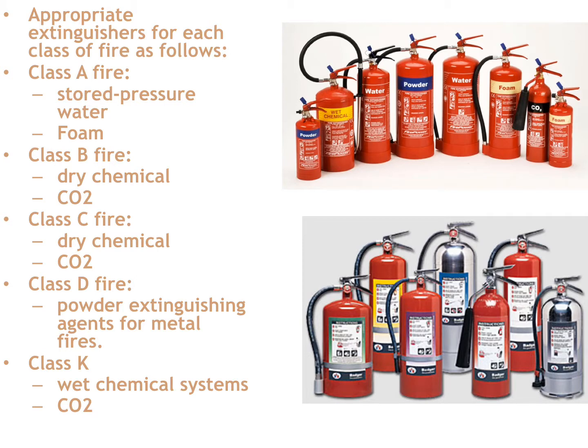The water with foam is going to help cool and smother your fire. For a Class B fire, you're going to want to use a dry chemical or CO2 extinguisher for liquid or gas fires. A dry chemical extinguisher works really well for spraying on the surface and coating, and the CO2 extinguisher works by removing oxygen from the immediate area and helping cool it.